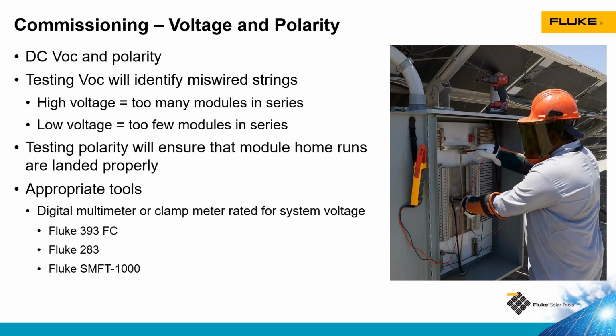I want to point out the meter that's shown in this picture. This is a 393 clamp meter. This is 1,500 volt rated category 3. With most meters, both clamp meters and multimeters, when you get reverse polarity, you just get that little negative symbol. If you're like this technician in the picture, it's hot outside, it's sunny, you're sitting there just going down all these different circuits in this combiner box, it's very easy to miss that little negative symbol.